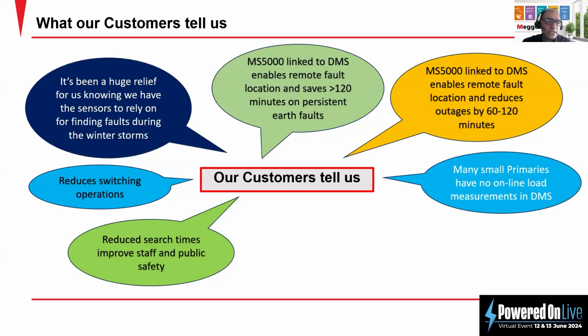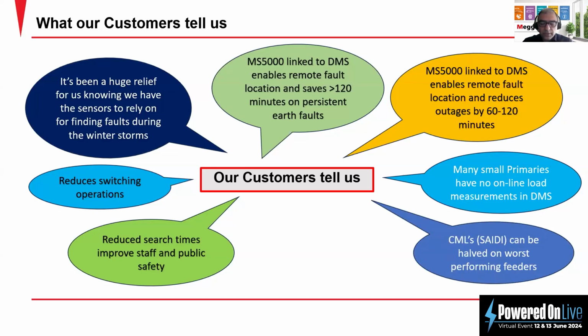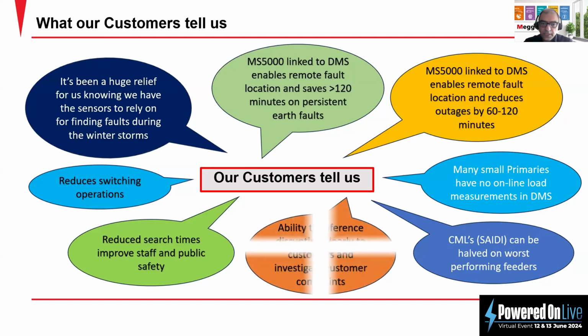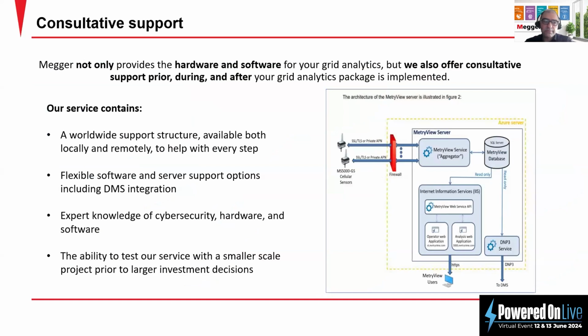minutes. Many small primary substations have no online load measurement in DMS, and they are using the system for a short time for online measurement and load management. Customer minute loss, or SAIDI, can be halved in the worst performing feeders, with the ability to reference a disruption clearly to the customer and investigate customer complaints.